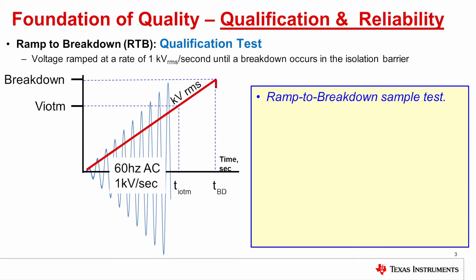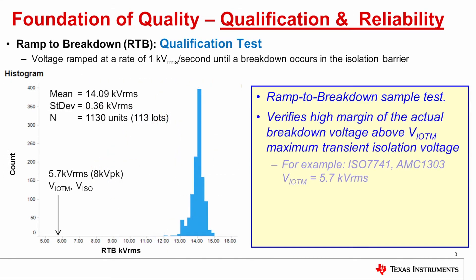Now let's look at the ramp to breakdown test. In the ramp to breakdown test, voltage is ramped at a rate of 1 kV RMS per second until breakdown occurs. When breakdown occurs, the breakdown voltage is recorded, and this is repeated on a population of units. Here's an example of this data. This is a data set of 1,130 units from 113 lots, and you can see that the mean value of the breakdown voltage is greater than 14 kV RMS. That is much higher than the requirement of 5.7 kV RMS for VIOTM and VISO. The standard deviation is 0.36 kV RMS.